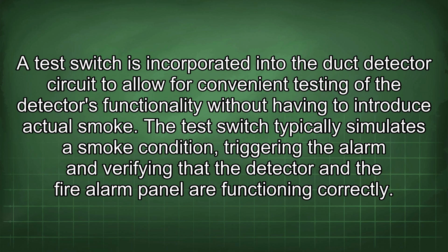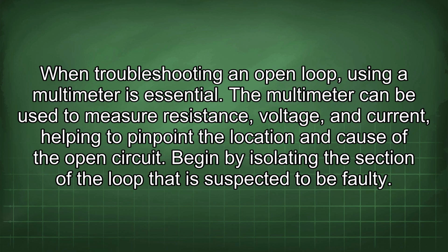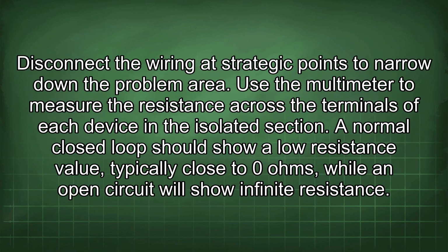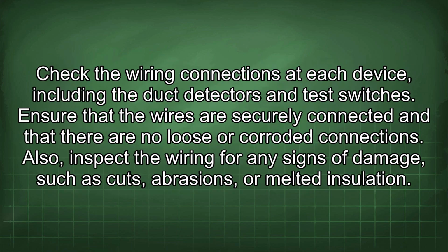panel are functioning correctly. When troubleshooting an open loop, using a multimeter is essential. The multimeter can be used to measure resistance, voltage, and current, helping to pinpoint the location and cause of the open circuit. Begin by isolating the section of the loop that is suspected to be faulty. Disconnect the wiring at strategic points to narrow down the problem area. Use the multimeter to measure the resistance across the terminals of each device in the isolated section. A normal closed loop should show a low resistance value, typically close to 0 ohms, while an open circuit will show infinite resistance.